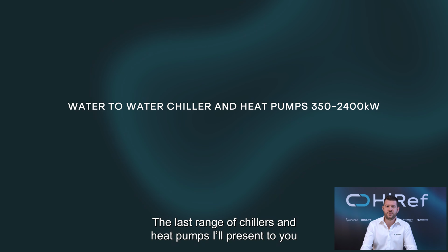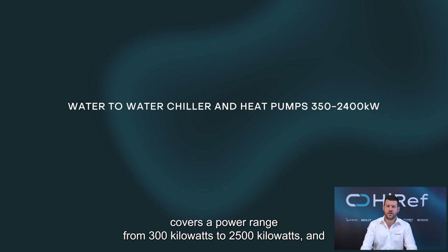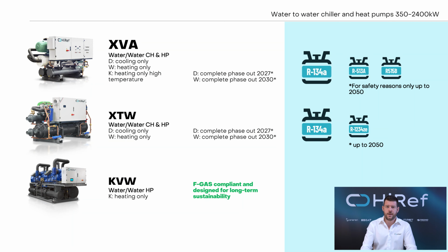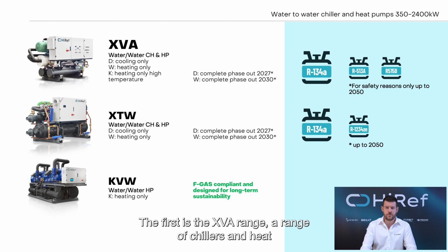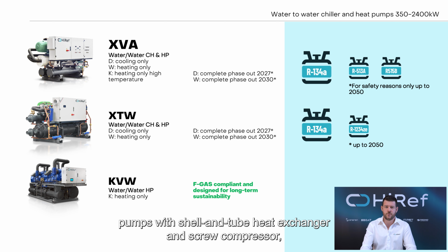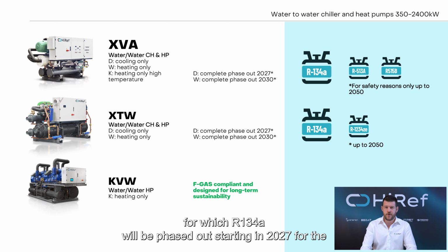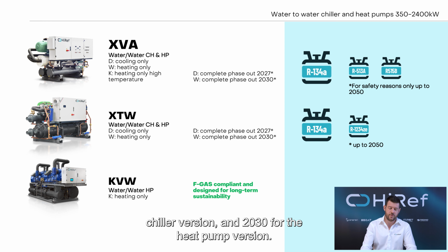The last range of chiller and heat pumps I present to you covers a power range from 300 to 2.5 megawatt, and is mainly made up of three ranges. The first is the XVA range, a range of chiller and heat pumps with the shell and tube heat exchanger and screw compressors, for which 134A will be phased out starting in 2027 for the chiller version and 2030 for the heat pump version.